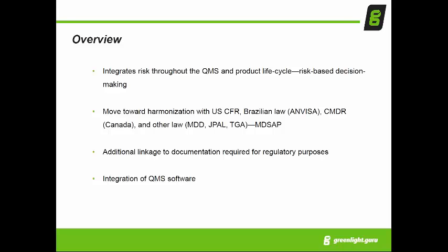And that's one of the biggest changes to the ISO 13485 is this concept of a risk-based quality management system. And the 13485 standard puts a lot of weight, a lot of emphasis on the risk management principles and processes that are described in ISO 14971. For those of you who are new to this industry, you need to find out more about ISO 14971. You need to find out more about ISO 13485. You can contact me. I'll have my contact information here in a few moments to share with you. But we've written some guides for those things to help walk you through that process.